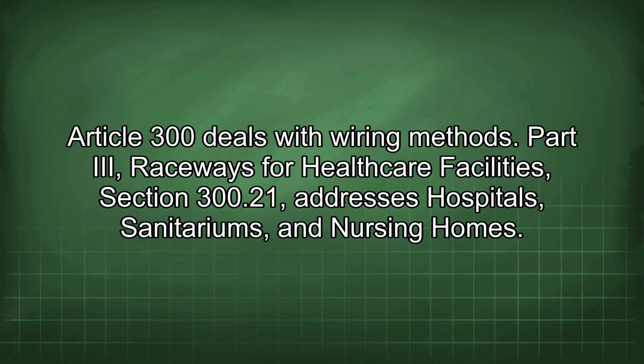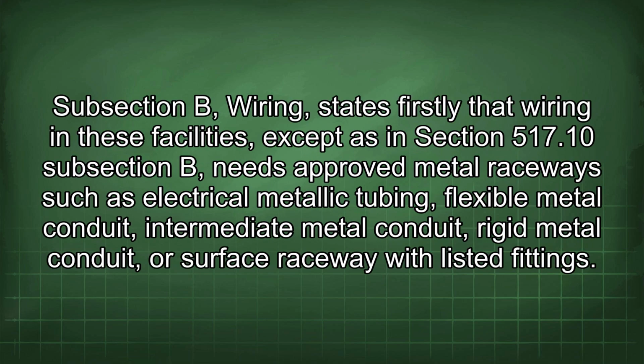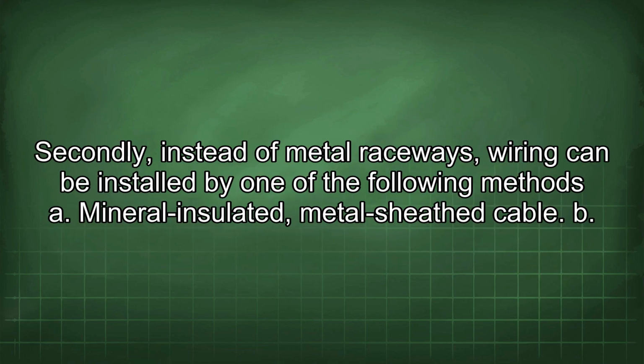Part Roman 3, Raceways for Healthcare Facilities, Section 300.21, addresses hospitals, sanitariums, and nursing homes. Subsection B, Wiring, states firstly that wiring in these facilities, except as in Section 517.10 subsection B, needs approved metal raceways such as electrical metallic tubing, flexible metal conduit, intermediate metal conduit, rigid metal conduit, or surface raceway with listed fittings. Secondly, instead of metal raceways, wiring can be installed by one of the following methods.